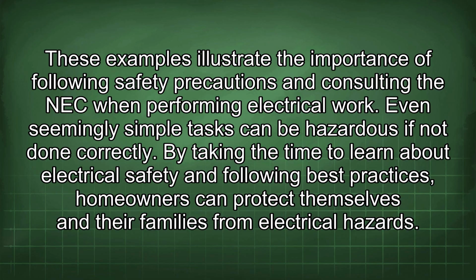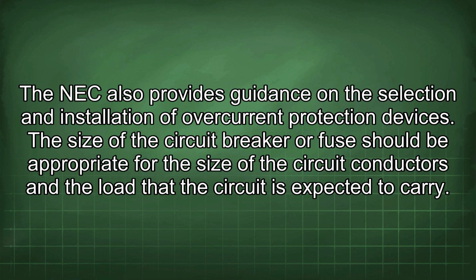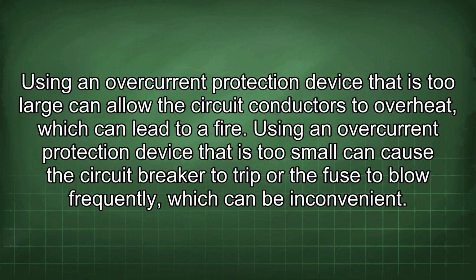The NEC also provides guidance on the selection and installation of overcurrent protection devices. The size of the circuit breaker or fuse should be appropriate for the size of the circuit conductors and the load that the circuit is expected to carry. Using an overcurrent protection device that is too large can allow the circuit conductors to overheat, which can lead to a fire. Using an overcurrent protection device that is too small can cause the circuit breaker to trip or the fuse to blow frequently, which can be inconvenient.